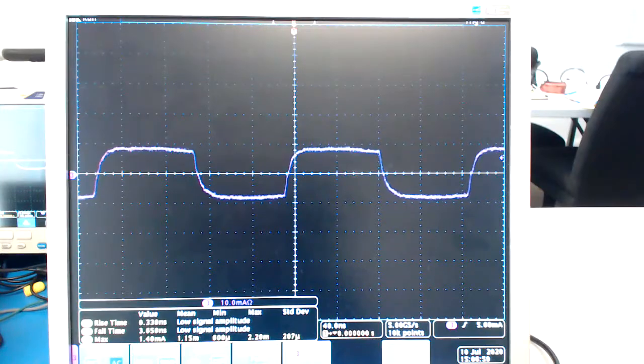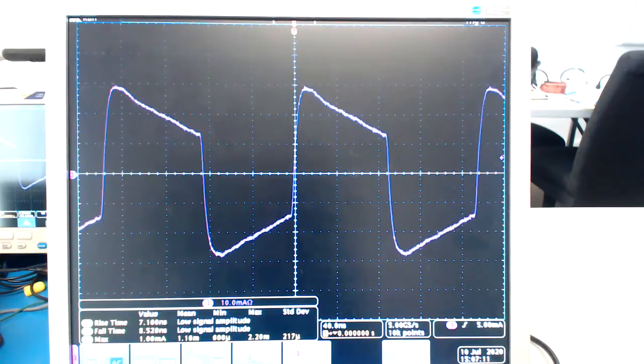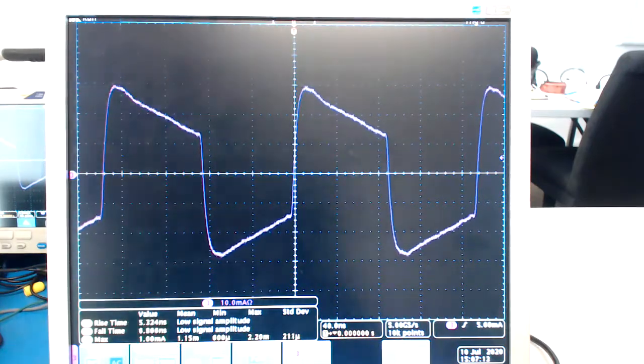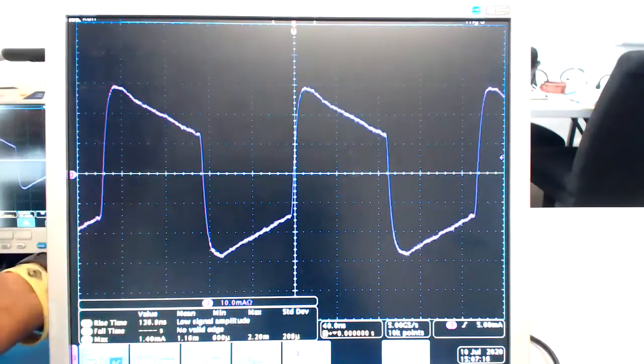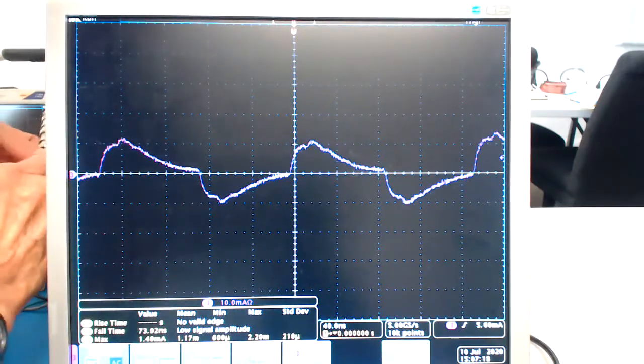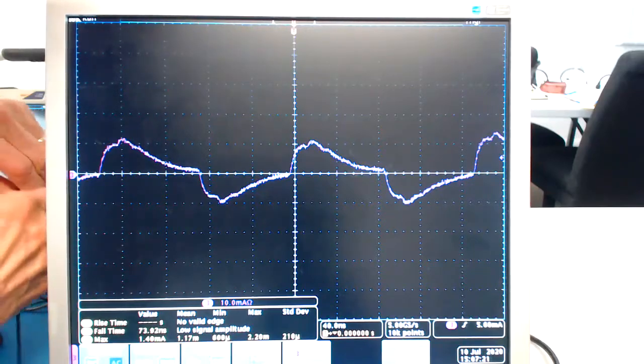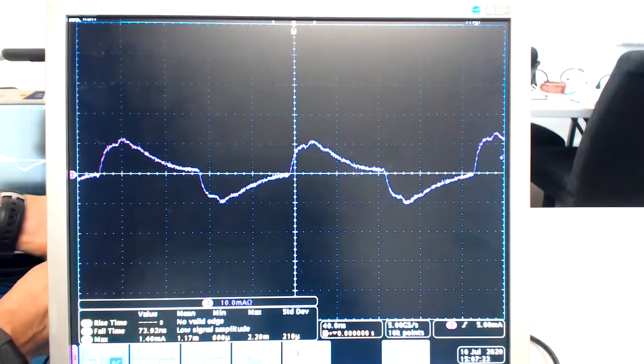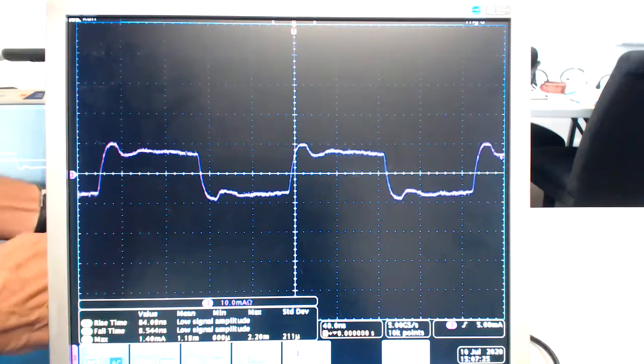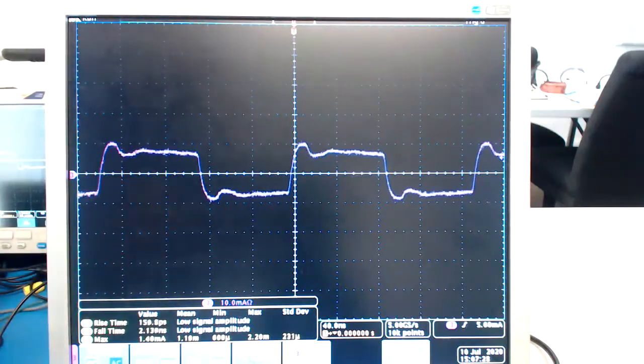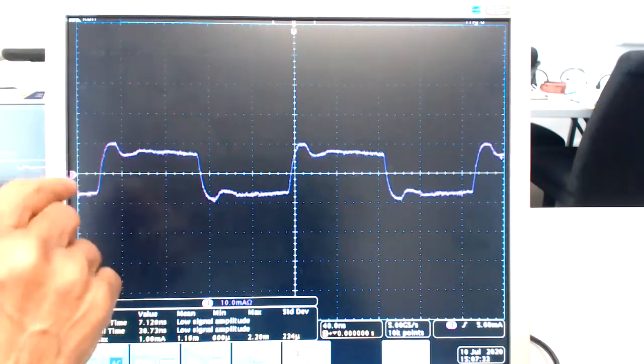Now, if I take those terminations you saw in the current probe, and I'll take them off here, put the current probe on directly, things get a lot bigger, but the waveform is not very square anymore because of the low frequency response of the current probe. Now I'm going to move the terminations to the scope, which is actually in back of this display. You can't really see it. Now it's on the front of the scope. And you see now we have a bump here.